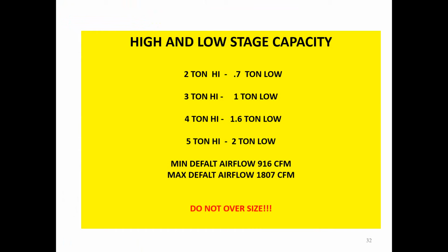So this is my chart again on the 2-stage product, on the variable capacity product. And so a 2 ton will go down to right at 3/4 of a ton. A 3 ton goes down to a 1 ton. A 4 ton goes down to 1.6, and a 5 does 2. Again, we've got the minimum airflow and the maximum airflow.